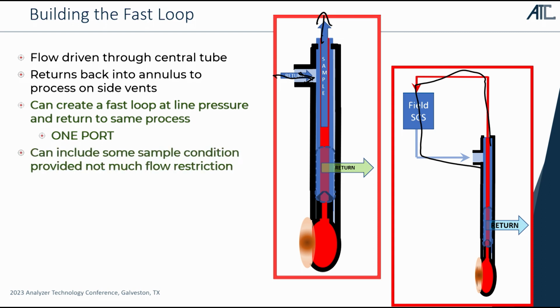One port of entry. We can even include a little bit of sample conditioning in there. We can put a bypass line with a filter there. Or we can put an inline sensor in there, like a Raman probe, or an NIR cell, or an oxygen probe, or a pH probe. So if you've got a water application, you say, I'd like to have a pH probe that I can actually maintain. I could put a probe like this in, put isolation valves on either side of the return side, nice big bore ball valves or gate valves. Again, I don't want flow restrictions. And then I just have it flow over my pH probe.